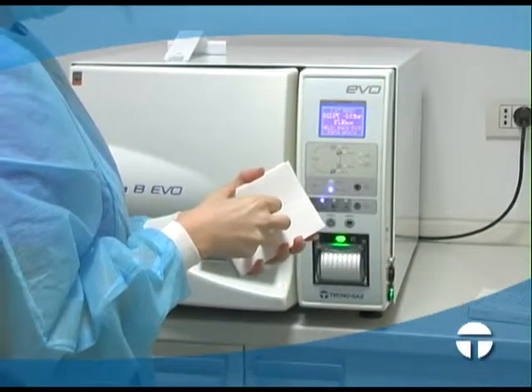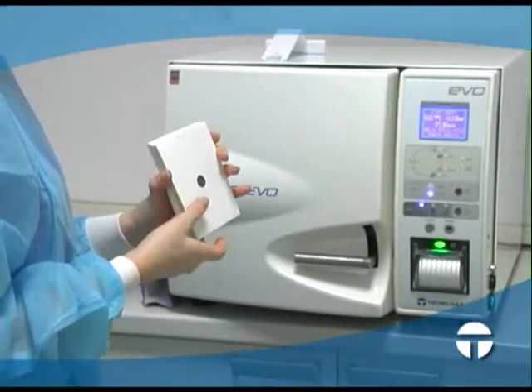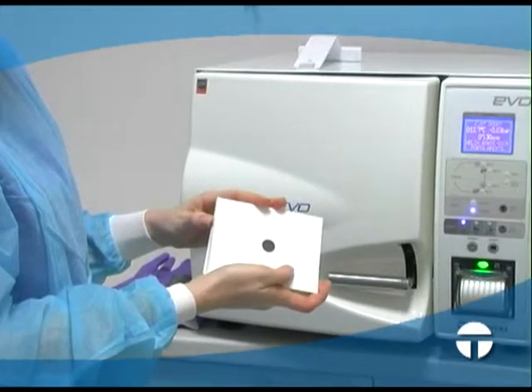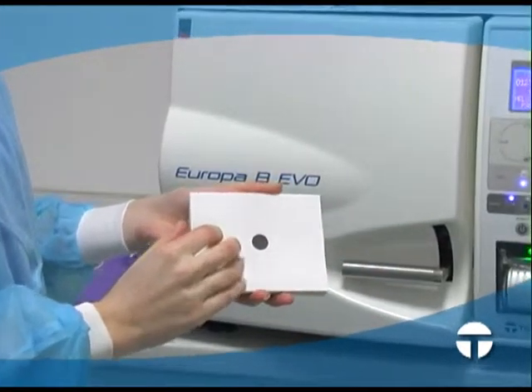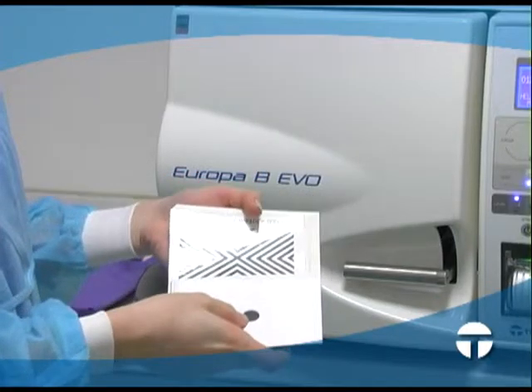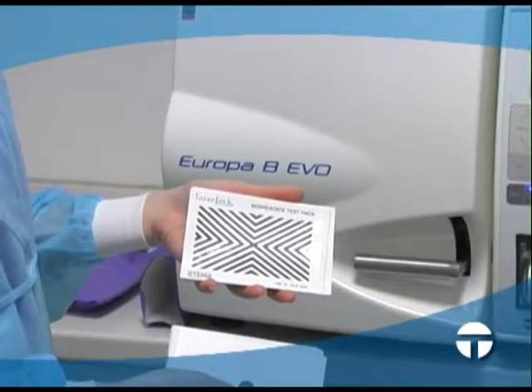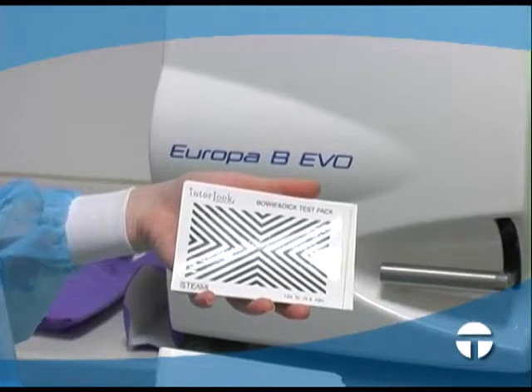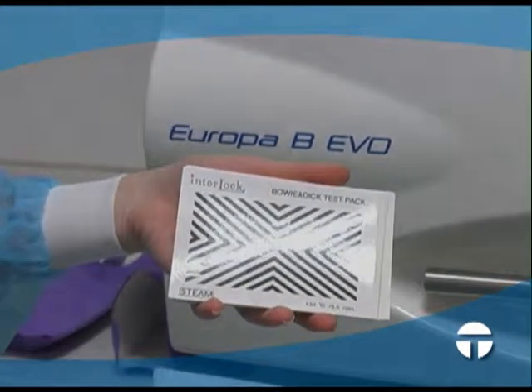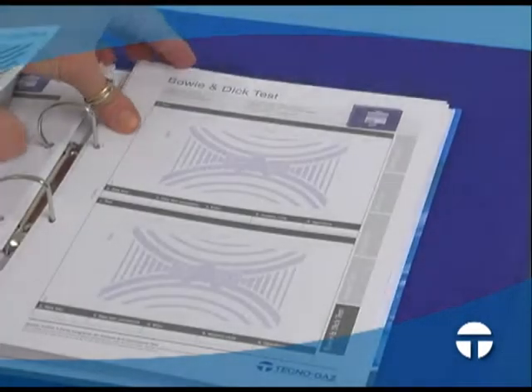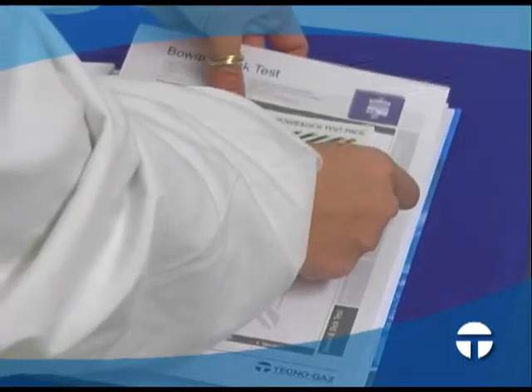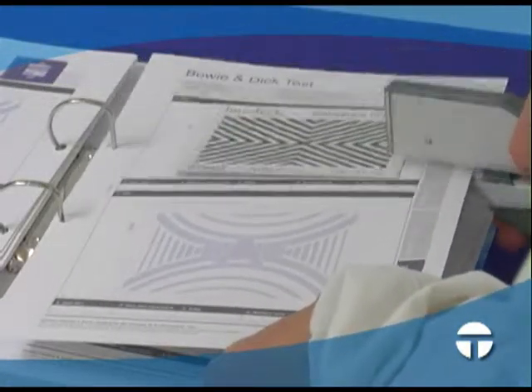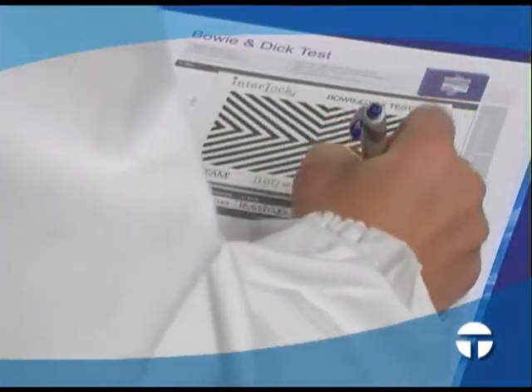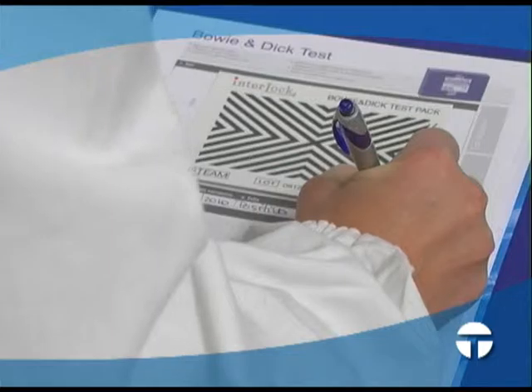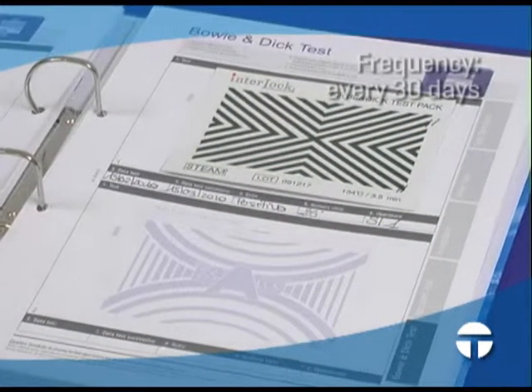If the test sheet has changed color correctly, it will be dark grey. Otherwise, the test result will be negative. If a negative test result is obtained, repeat the test. If the result is negative for a second time, stop using the appliance and immediately call an authorized technician. Date the test and file it normally. Only those autoclaves certified for sterilizing porous loads have to pass this test. We recommend testing every 30 days.